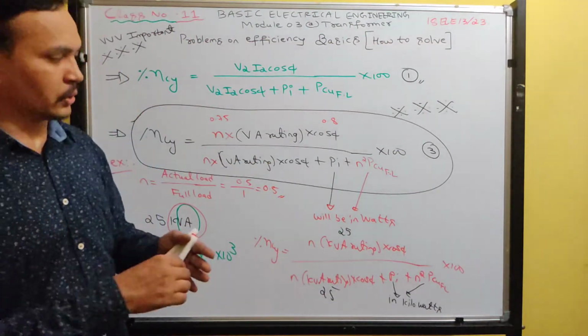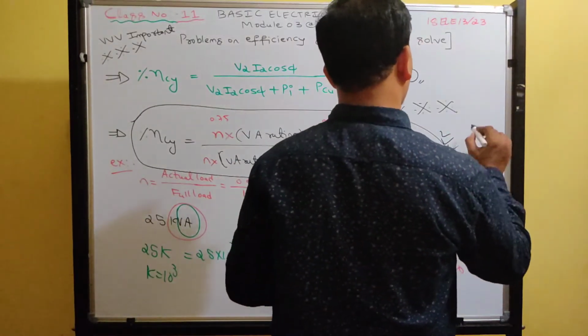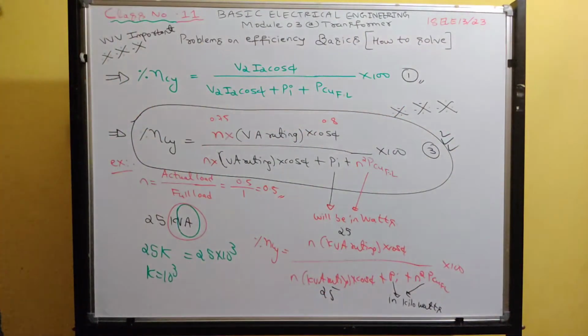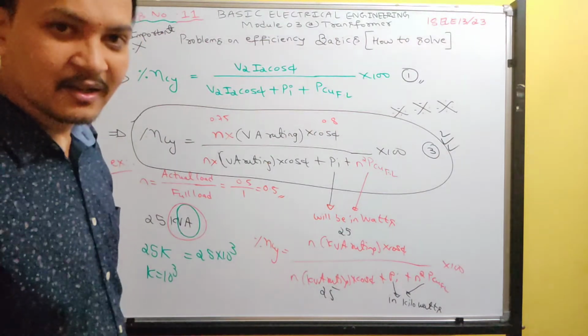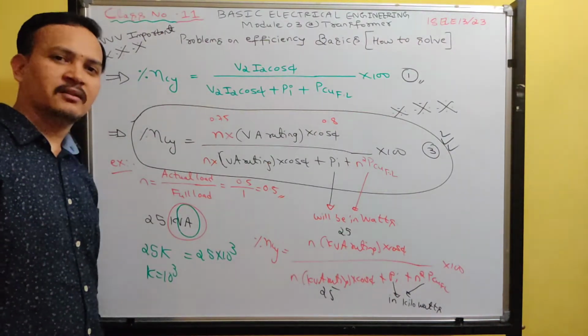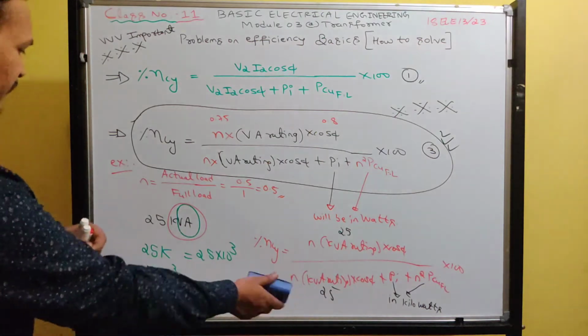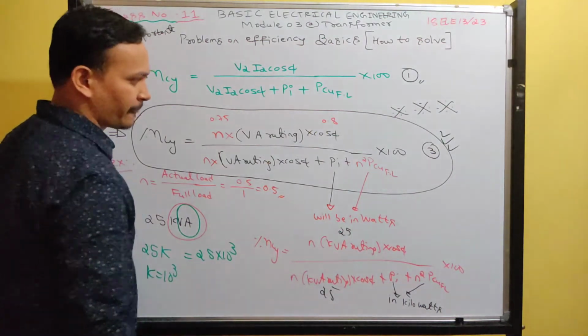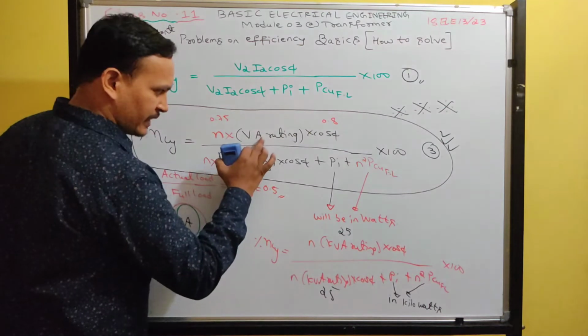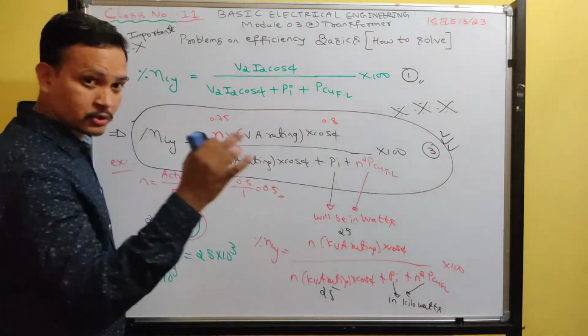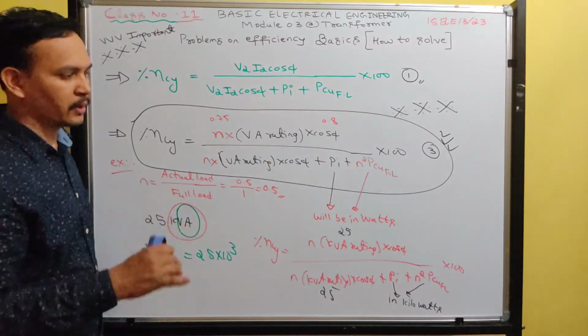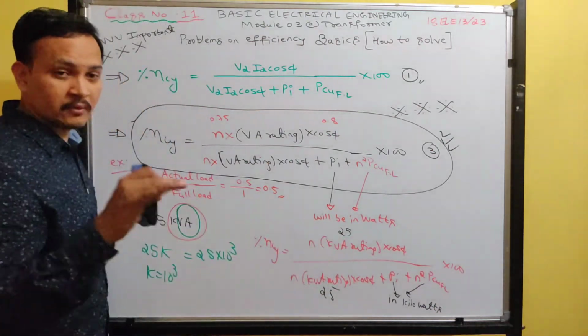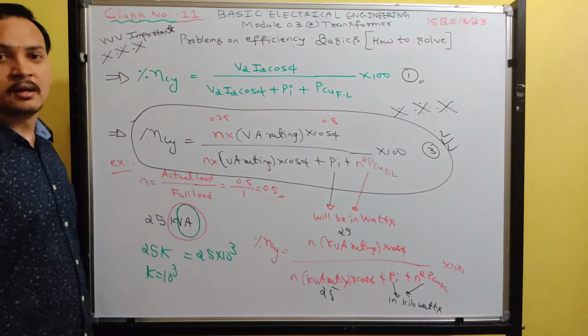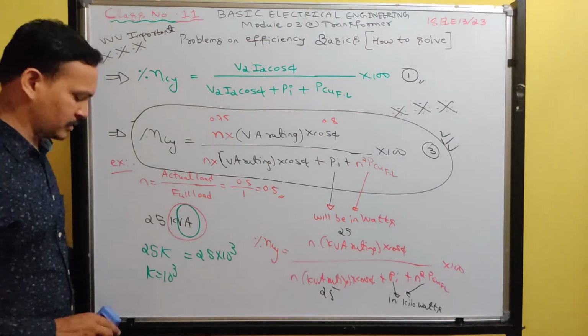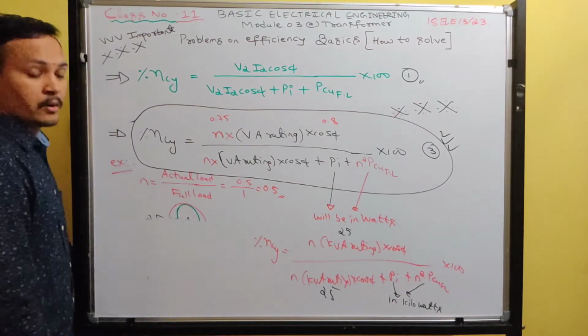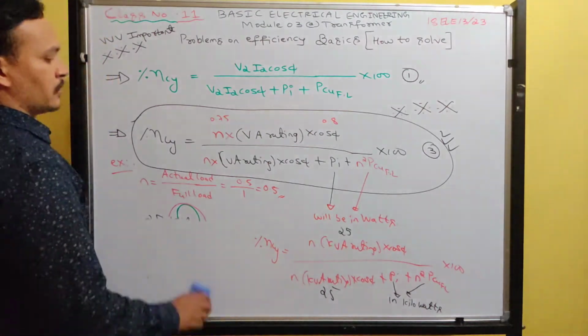So I recommend you to refer to equation 3. Equation 3 is valid to determine efficiency at any power factor and any loading condition. Keep in mind, if you use VA rating, your iron and copper losses should be written in watts. If you use kVA rating, your iron and copper losses should be written in kilowatts. That is important. Pause the video and then copy it out.